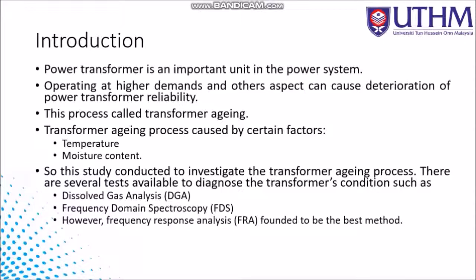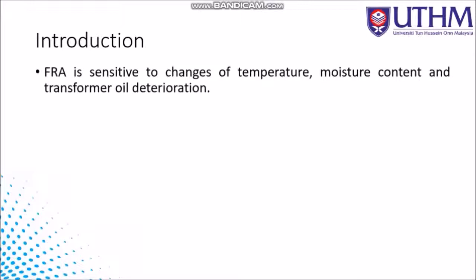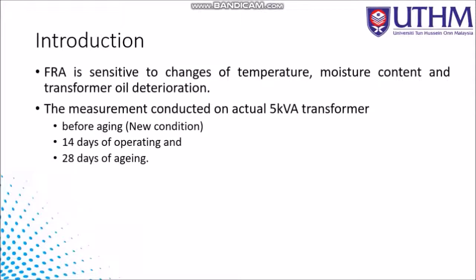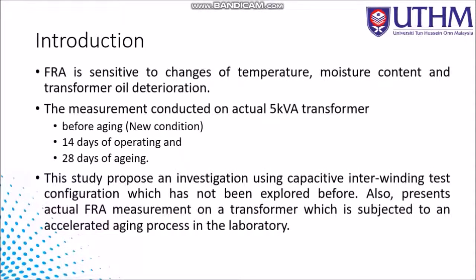There are several tests available to diagnose the transformer condition, such as dissolved gas analysis, frequency response, and frequency domain spectroscopy. However, frequency response analysis (FRA) is found to be the best method to diagnose transformer mechanical condition and other failures. FRA is sensitive to changes of temperature, moisture content, and transformer oil deterioration. Measurements were conducted on an actual 5 kVA transformer before aging in new condition, after 14 days of operating, and after 28 days of aging.